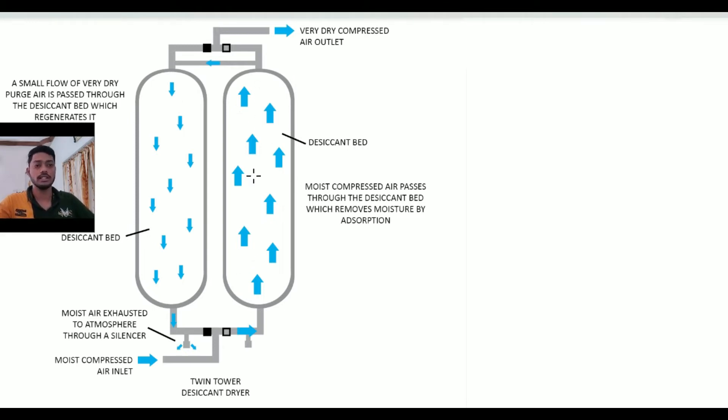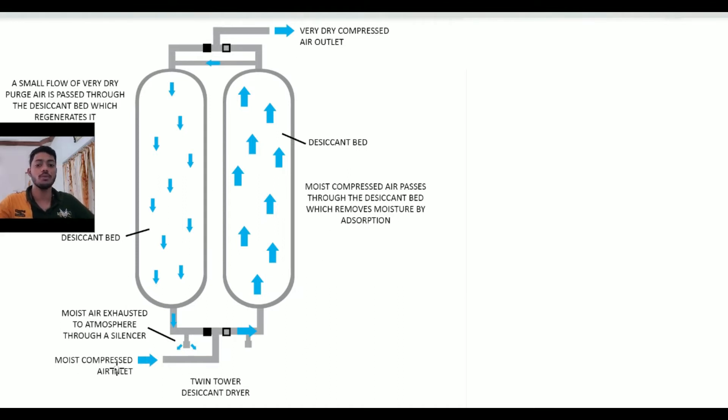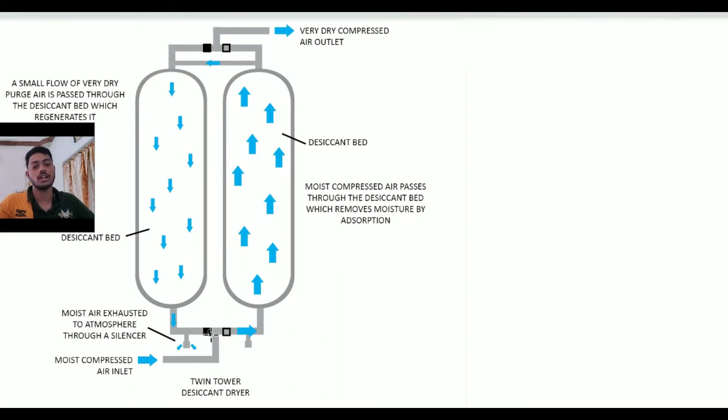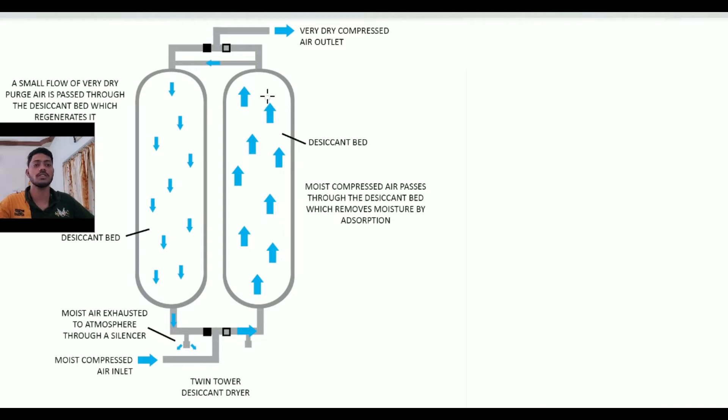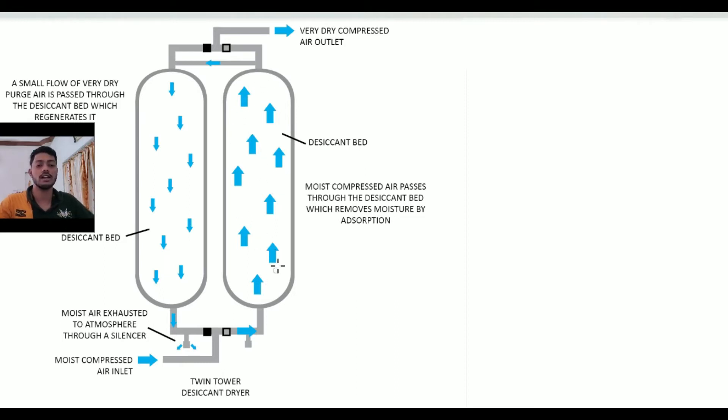Here the right cylinder is processing for the air drying process. The compressed moist air coming from the compressor is coming inward through this inlet section. The left cylinder valve is closed and right cylinder valve is open, so the air can move upward from the bottom of the cylinder to the top.